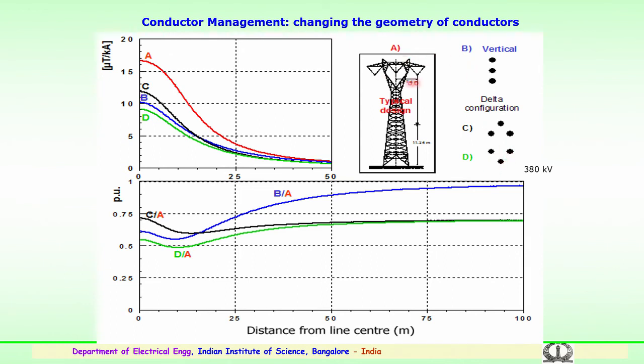For example, this is one type of arrangement where the conductors have been connected, and these are the clearances. B is the vertical conductor placement, as shown here. Third is the delta configuration in a rectangular equilateral triangle type, and D is the inverted equilateral triangle. The placement of the conductors is being modified, and studies have been carried out to see the field behavior. You can see here for the magnetic fields, it is in micro tesla per kiloamp. So, it depends on the current rating, or the load, carried by these conductors.